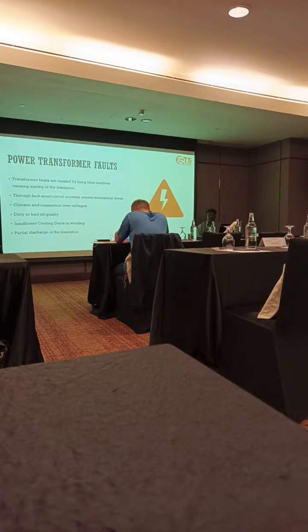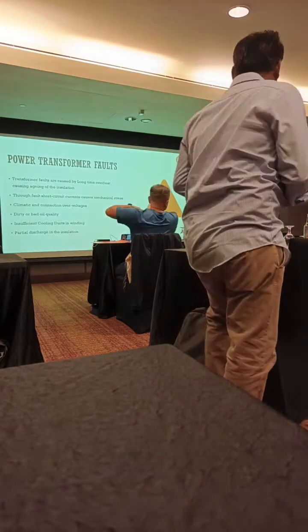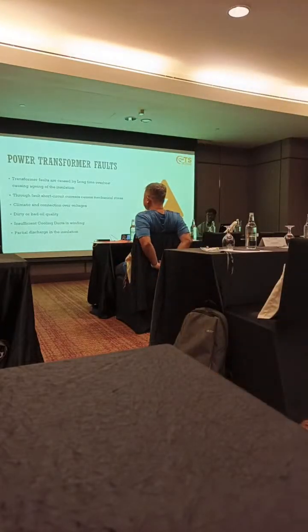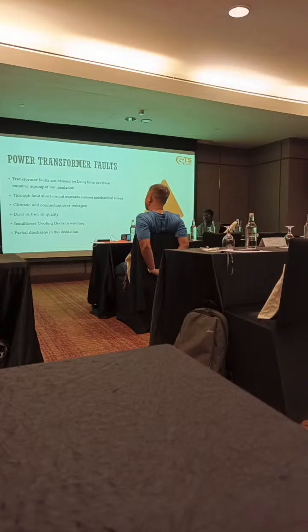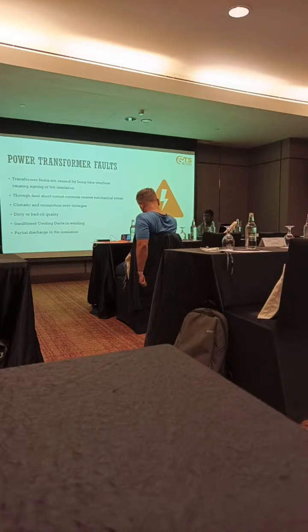The windings are like that, so it is filled with oil. Coming back to the oil, this oil will serve two purposes. One is as a cooling medium for the transformer. Why? Because the core and the winding will heat up once you start charging the transformer, so we need to maintain the temperature. So the transformer oil will act as a cooling medium in one case. In another case, it will also act as an insulation between the tank and the winding.